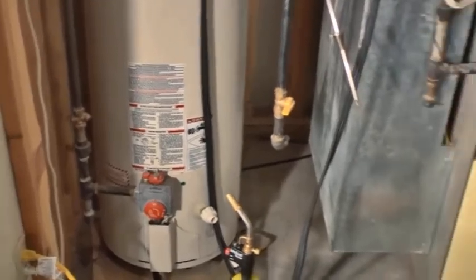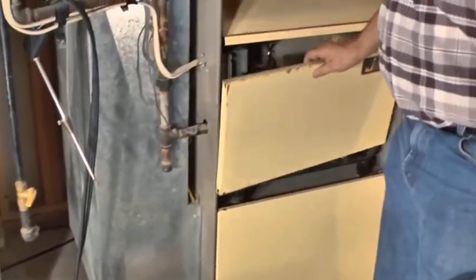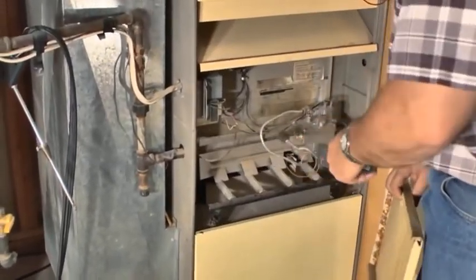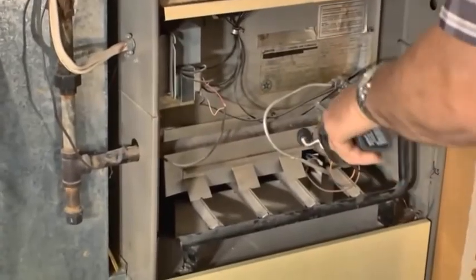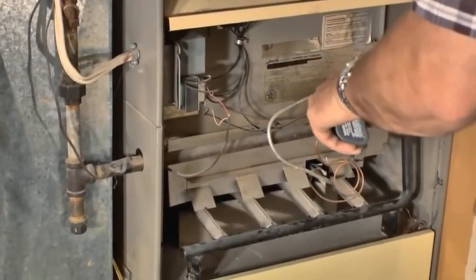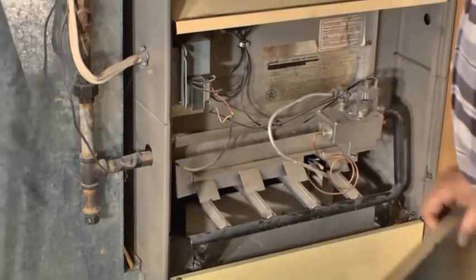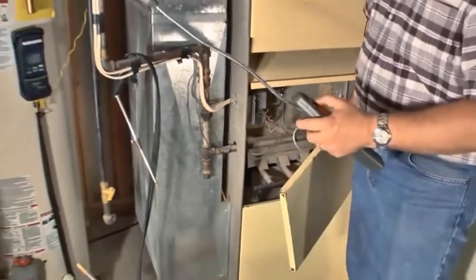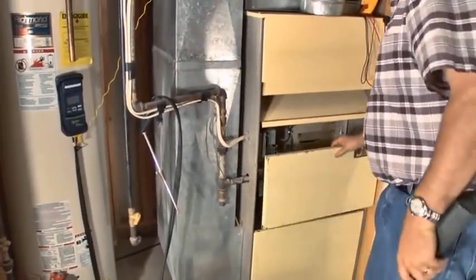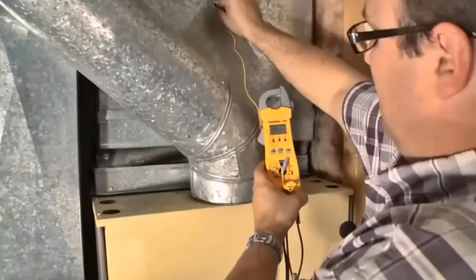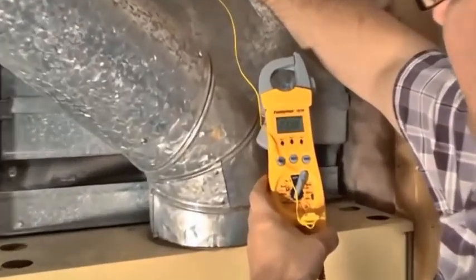Looks like we're pretty good. I'll even check inside the furnace a little bit. Sometimes you can have a cracked gas valve. And it looks like we're good there. Okay, we're at our 5 minute mark.